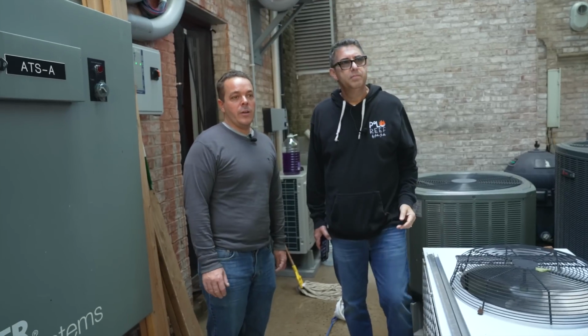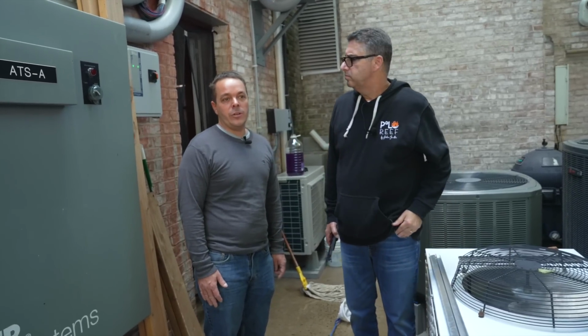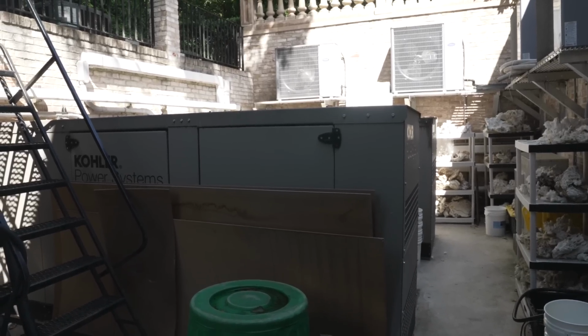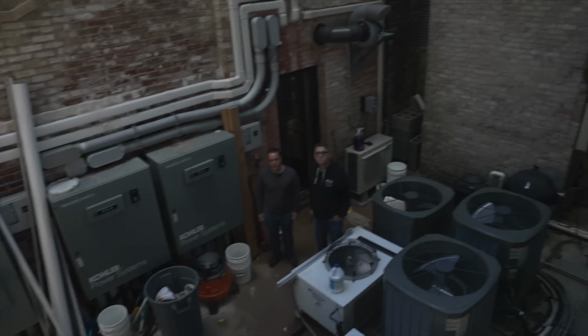So we have twin 125 kW generators from Polo, 1 for each 800 amp service. These are the transfer switches for them, so that when we lose utility power, we automatically switch to these natural gas generators. It's almost a seamless transition. I mean, they exercise every Monday, and the unique part of it is now they're on our main computer. Our computer monitors them via Modbus, which is a communications protocol, for any errors, low oil, water temperature, and things like that. So no surprises during a storm.